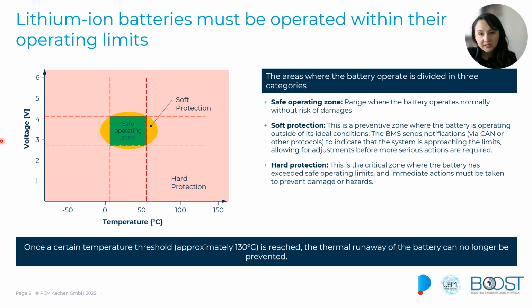The safe operating area may include different areas. Here we are showing some of those. First, we have the hard protection, that is everything with the red shadow, and these hard protections are triggered when the safe operating area is exceeded.